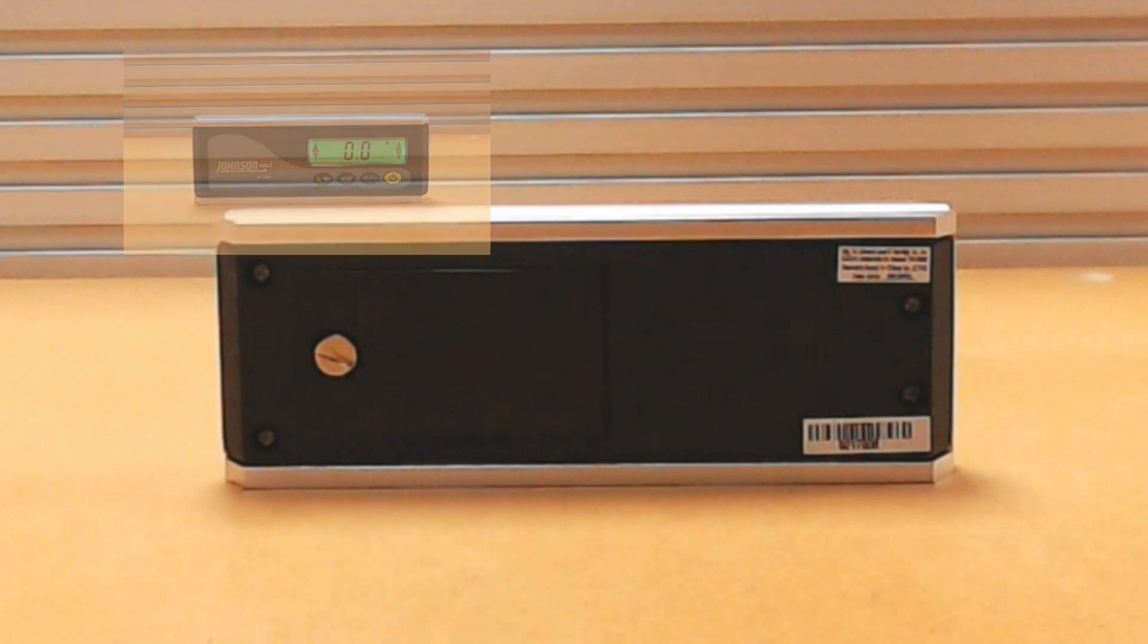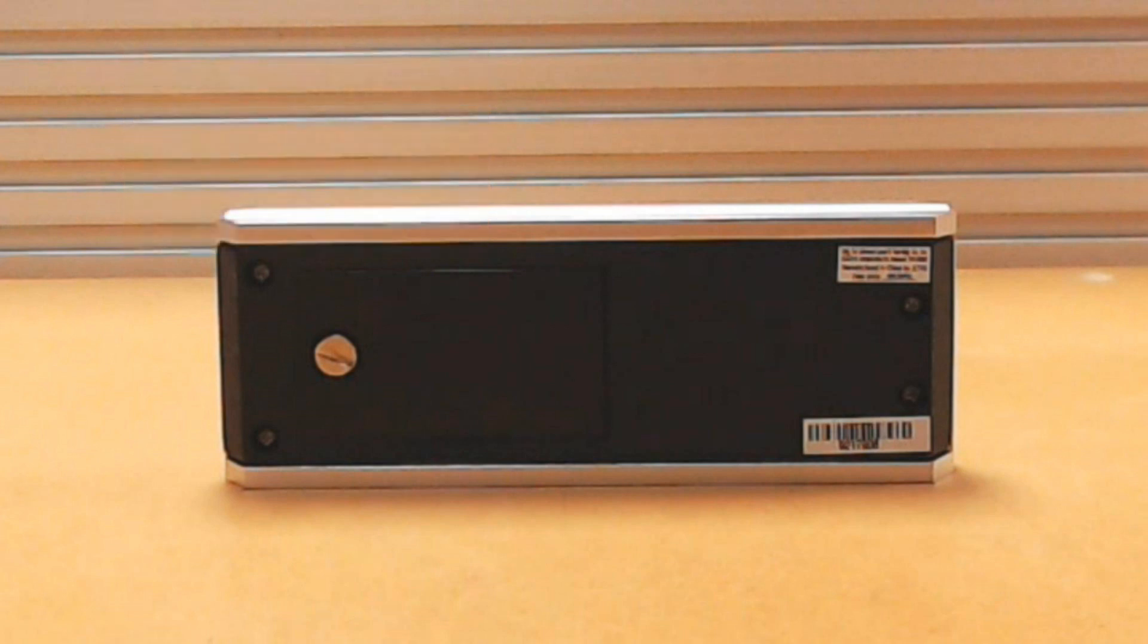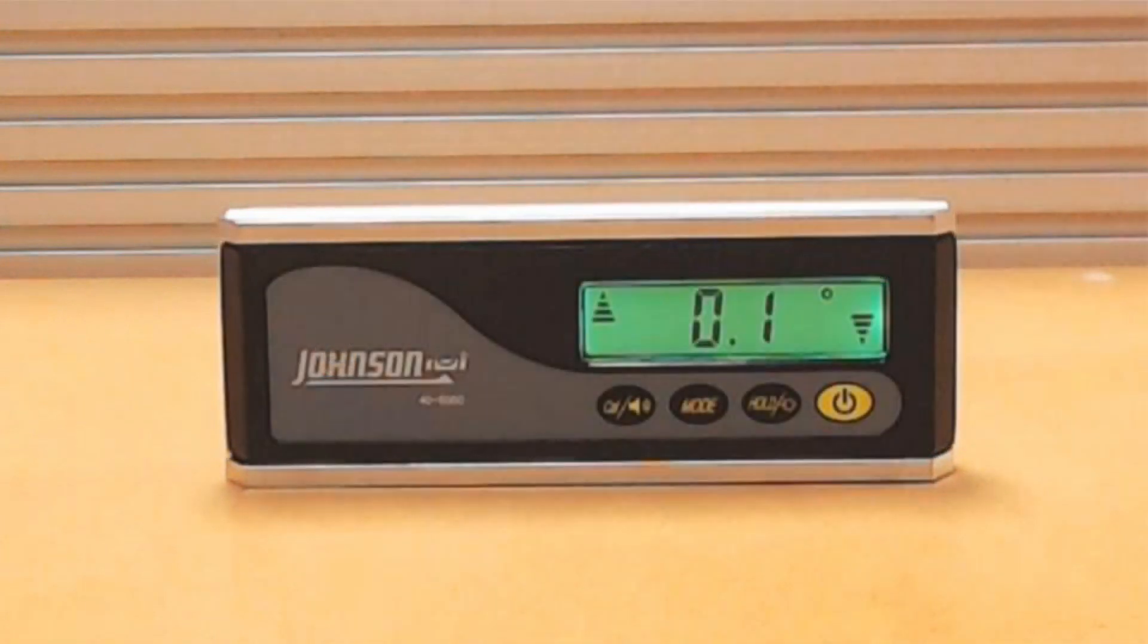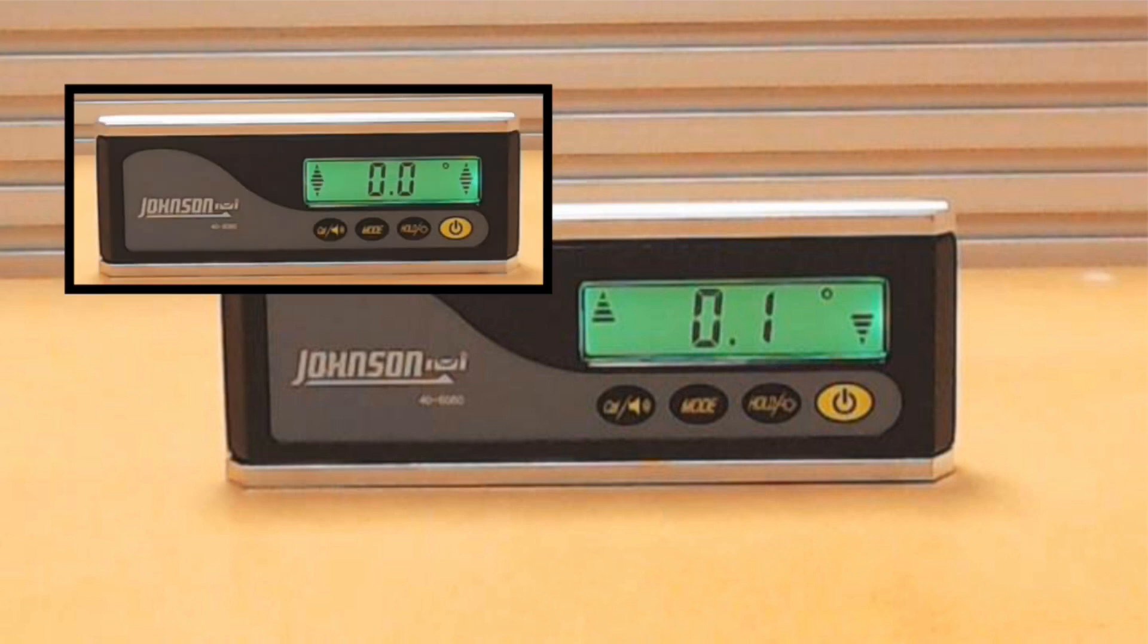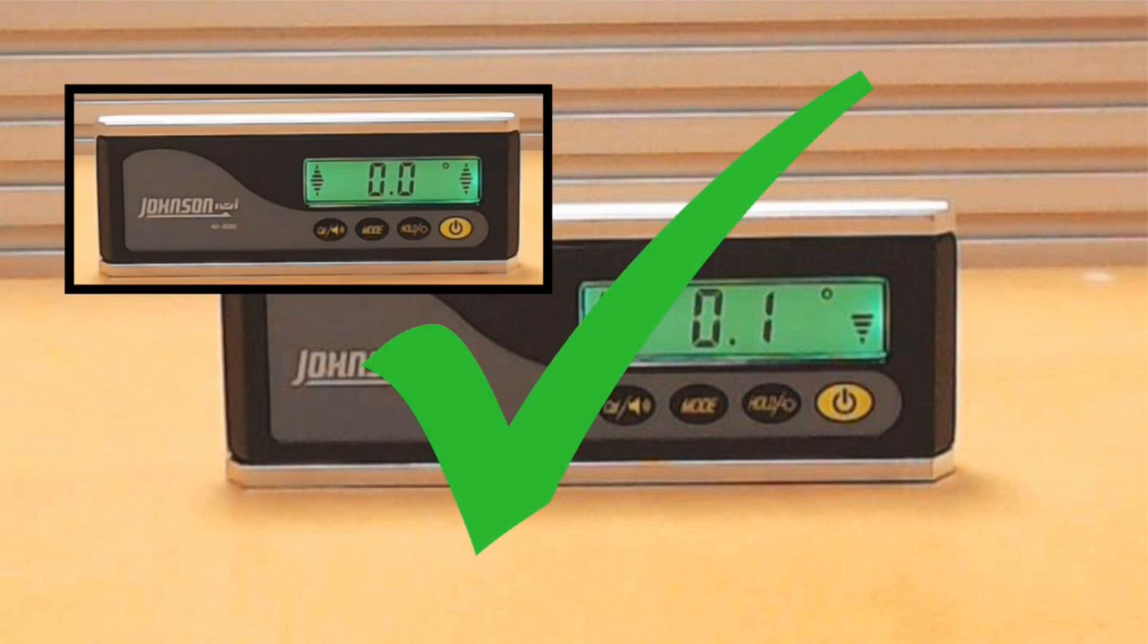Verify the new calibration. If the inclinometer has not been properly calibrated, find a more appropriate reference surface and repeat the calibration procedure.